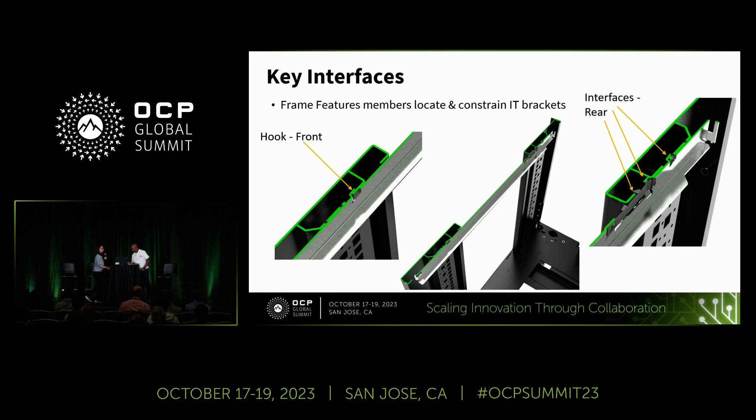Now I'll hand it over to Indro. In this slide, I'll walk through the internal key interface. You can see the cross section of the frame along with the shelf. The shelf kit is fitted tool-lessly — at the rear you can see how the shelf kit interfaces with the vertical, and at the front how it hooks in. The design ensures rails or servers won't come loose during deployment. The vertical also has square cutouts — RU and OU cutouts to support the shelf — and is designed to meet the EIA tolerance requirement.